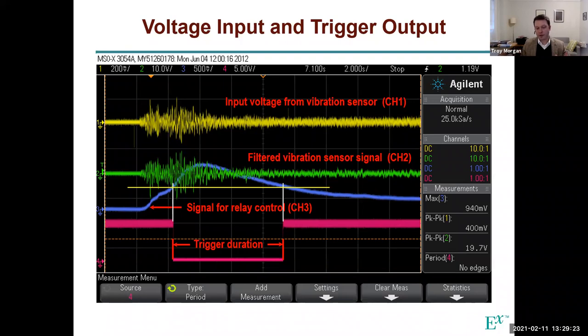It was 5 seconds that was the threshold for trip. I asked why 5 seconds, and they said that's because that's what the dial was set to. I said, but why was the dial set to that? It was just the max, the biggest number on there. So I said, okay, sounds good.